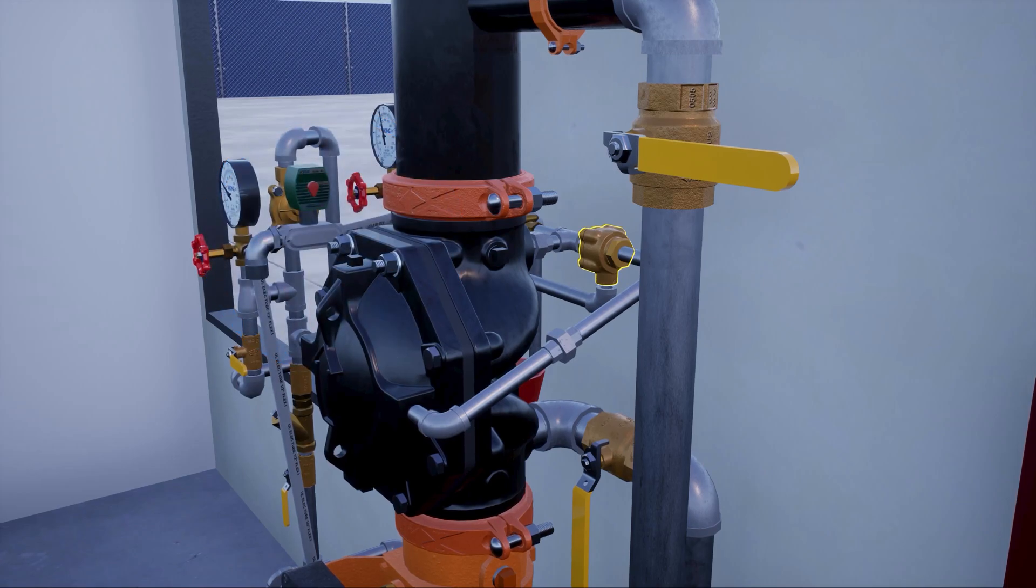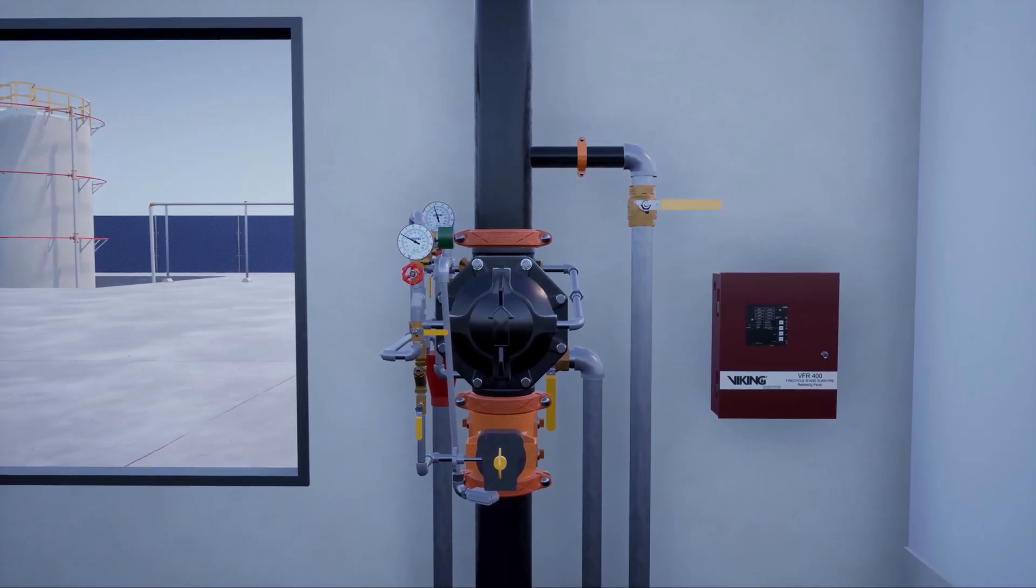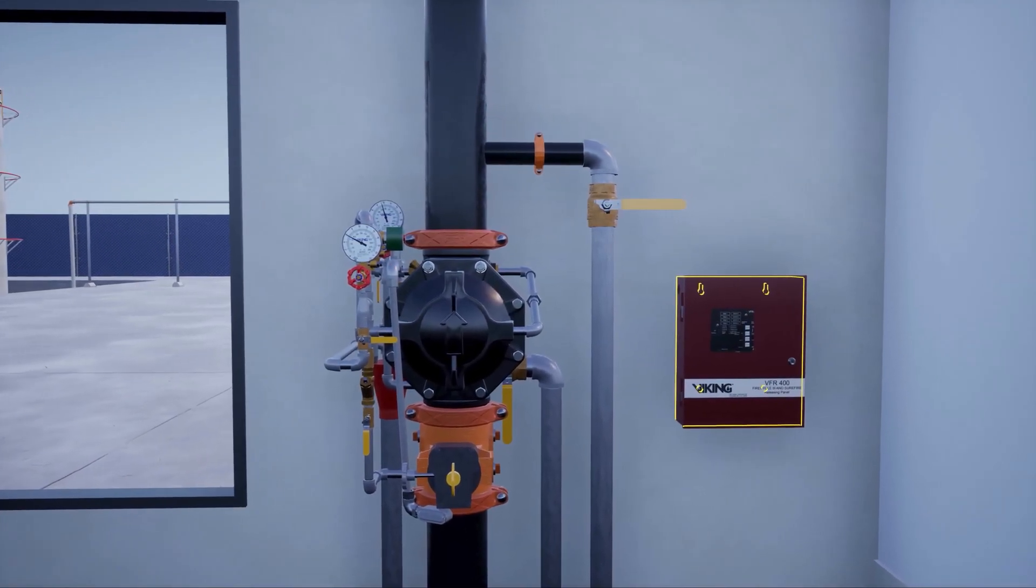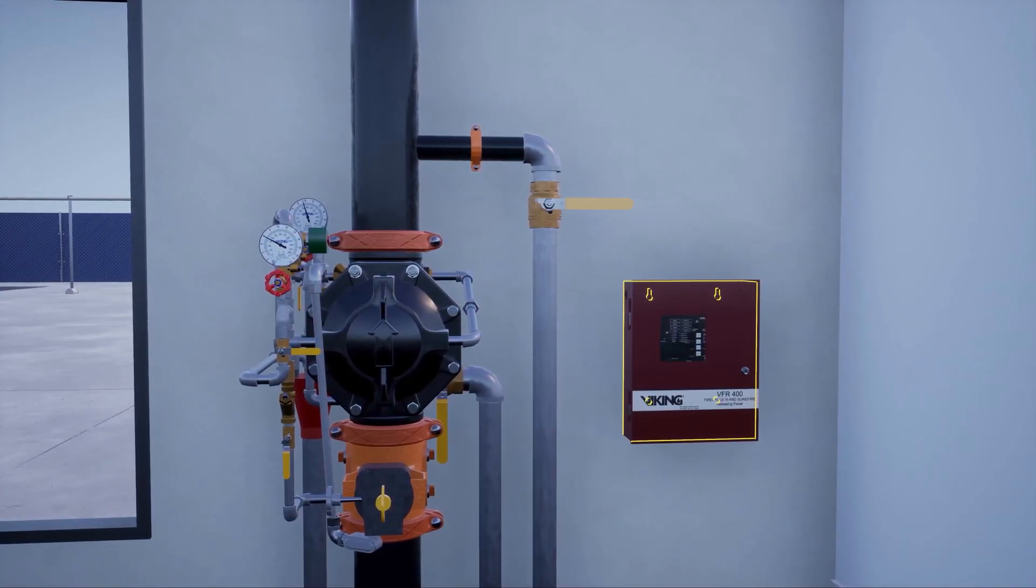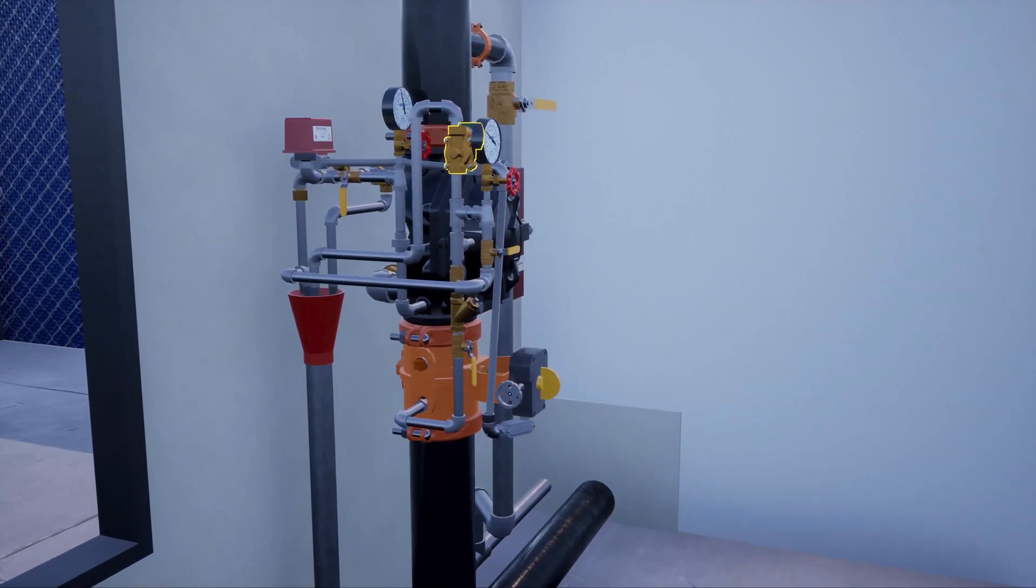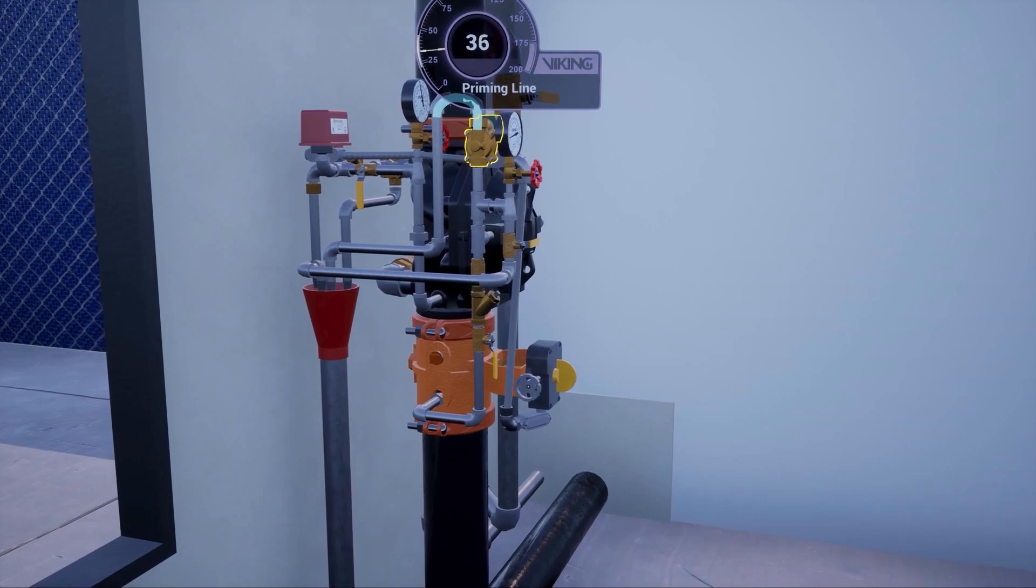In a scenario where a fire has started in or near the storage tanks, the electric detection device activates and sends a signal to the VFR 400 release control panel. The electric solenoid valve is powered open, releasing water pressure from within the priming chamber of the deluge valve.